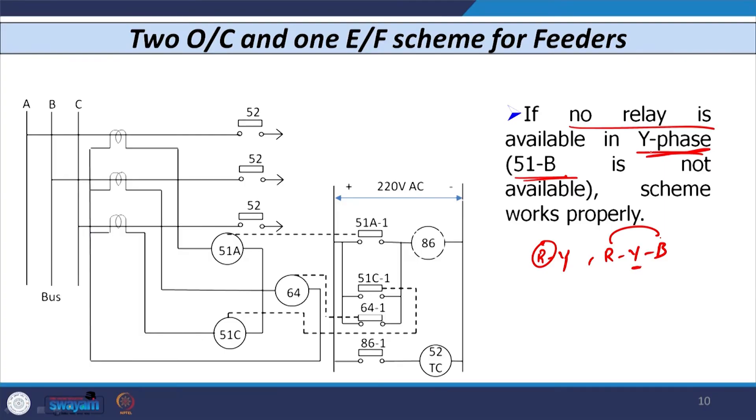The same applies to faults involving ground — line to ground, double line to ground, and triple line to ground. If you remove any one of the three phase units, the scheme still works perfectly well. The only disadvantage of this scheme is that whenever a star-delta transformer is involved — meaning any distribution feeder feeds to a transformer — there can be a possibility of delayed time of operation.